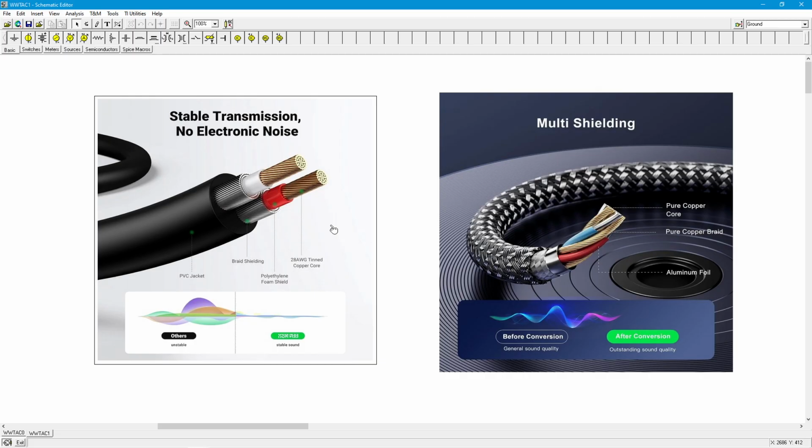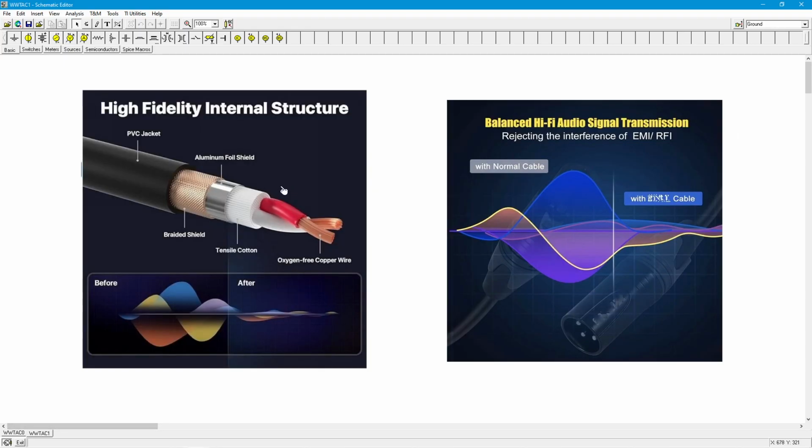They gave this to a graphic artist and said, here, come up with something. First of all, the shielding should cover both conductors. This is showing two separate shields. Secondly, these conductors are not twisted together, right? You should have an outer shield and then two conductors twisted together, right? I mean, at least this drawing made some sense, okay?